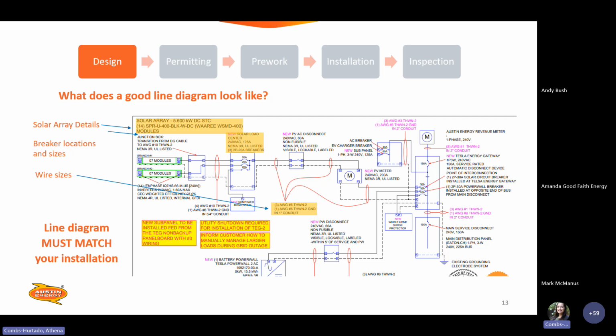Okay, so what does a good line diagram look like? So please make sure that when you submit these things, you've got a couple of things very detailed out. Solar array details, we want to see what's going on there. Breaker locations and the sizes. Also wire sizes. The line diagram must match your installation. So if there's any updates, please make sure you update and submit a new wire diagram.